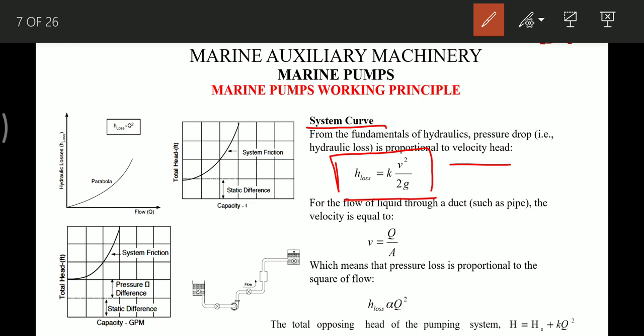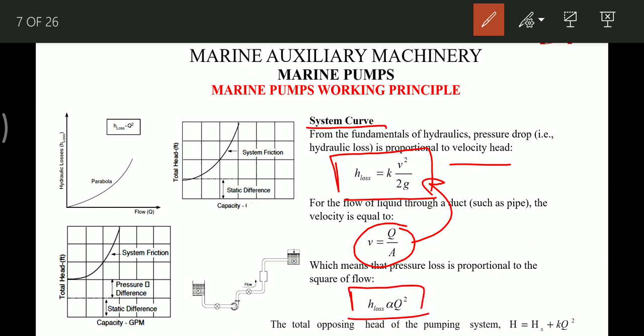Head losses in the system are of two types: frictional losses due to drag or viscosity, and losses due to components in the system such as valves, flanges, and changes in pipe diameter. Substituting velocity as Q/A into the equation, we find that head loss is directly proportional to the square of the flow rate — giving us the equation for a parabola, as seen in the graph.